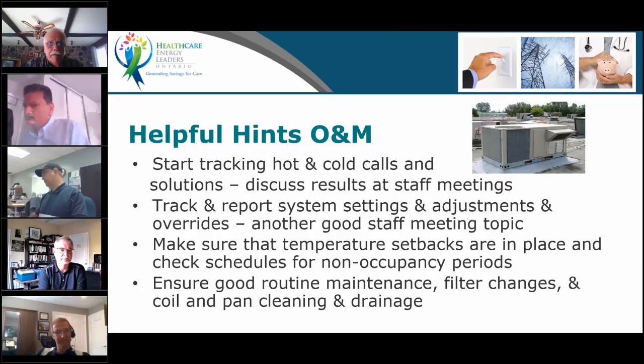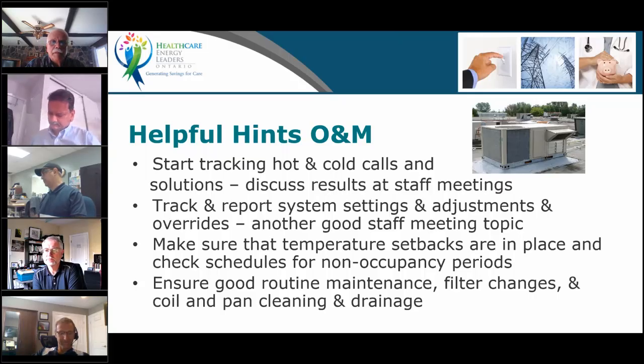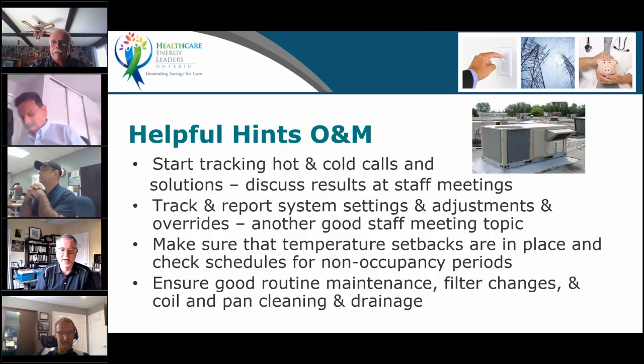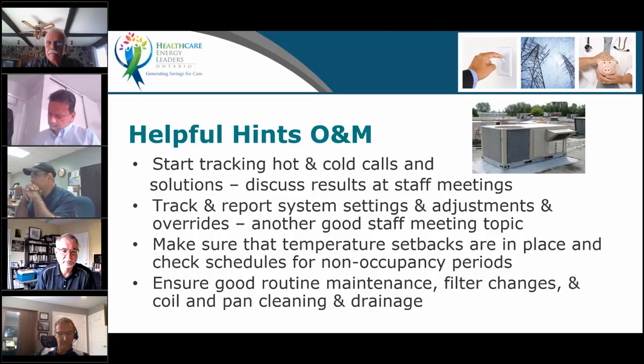For type 3 spaces, if you do schedule it off, you need to flush the space with 3 air changes before occupancy. You can decide to do half after occupancy and half before, but ASHRAE's guideline for COVID-19 operation is 3 fresh air changes if you schedule a system off. And obviously, you ensure good maintenance. Hospitals typically have MERV 8 pre-filters and MERV 13 or 14 filters, plus sometimes HEPA filters, depending on the spaces.